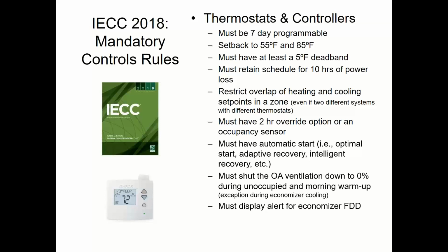There's only like 7 or 8 models of stats in the whole country that comply with everything on this list. So if you're going to use a thermostat instead of a building automation system, it's a very short list. I can send you that list. It's like 1 Venstar model number, 1 Carrier model number, and like 4 or 5 Honeywell model numbers. And that's it. Everyone else can't do all these things. It's pretty limited. They might do almost all these things. They may say that they're Title 24 compliant, which makes it sound like you do everything because California people are always the most strict. Well, they're not in this case. California is actually less strict. To do everything on this list, Title 24 isn't going to cut it. You have to do more than that.